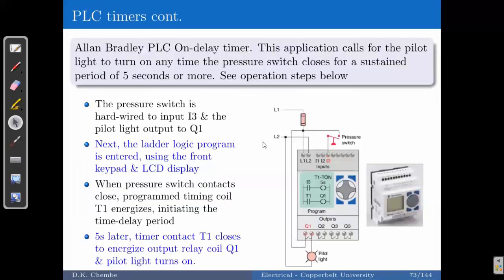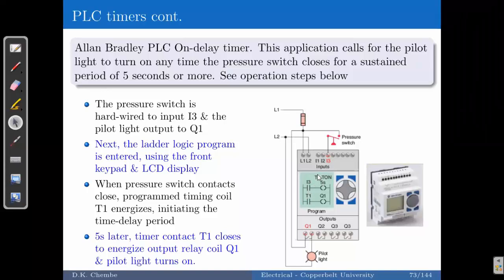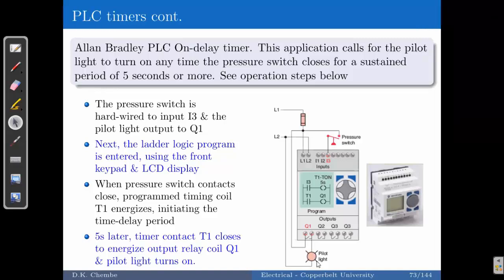Here is an example of a PLC. You have the input module where you connect all the inputs, including the supply L1 and L2, and a pressure switch which operates when pressure increases. The program can be written to create a time delay to bring on a light. Once the pressure increases and the switch closes, the I3 contact closes and activates the timing — the timer begins to count. After five seconds, Q1 gives the output signal and the light turns on.